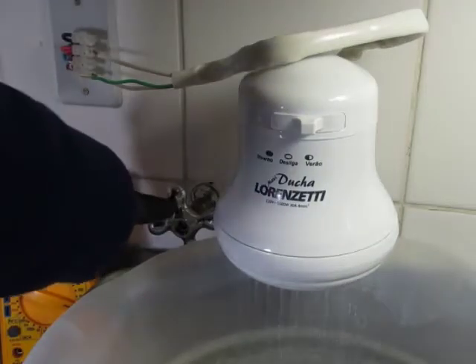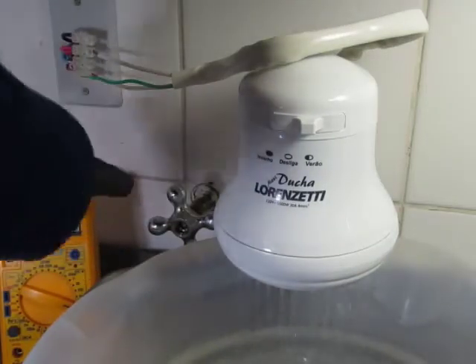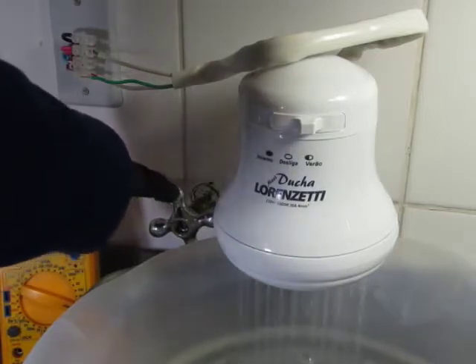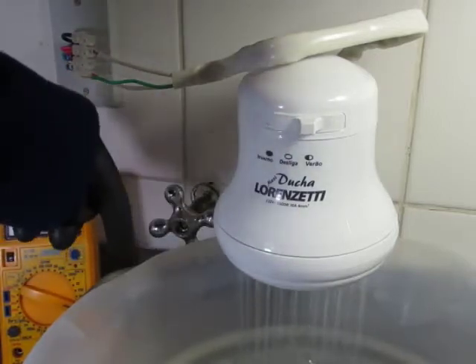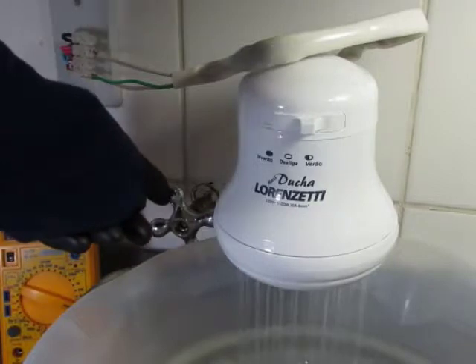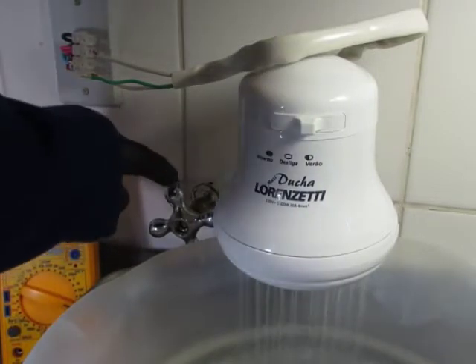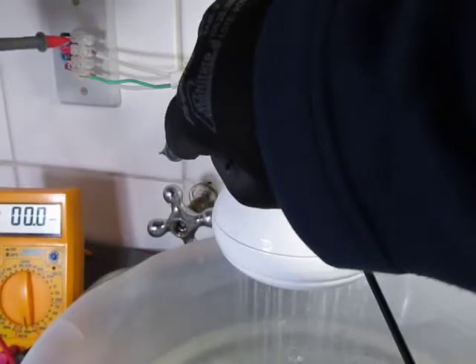You can see that this tap is made of metal and that is in contact with the water that goes into the shower head. I will disconnect the ground again and I will measure the voltage between the tap and the mains ground. Do not know if the camera can capture it, but we have here around 35 volts. And now, let us measure the leakage current between the tap and the mains ground. We have around 400 microamps.